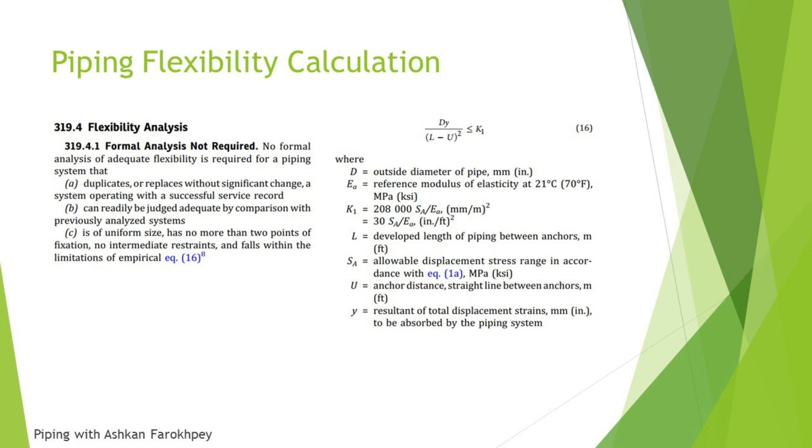In section B, the code says that a new system can readily be judged adequate by comparison with previously analyzed systems. It is just the same as paragraph A, section A. It says that if you have analyzed the system, stress analyzed the system, and you are making a new one just like the first one, you don't need to do stress or flexibility analysis. Both sections A and B are the same I think, because they are saying that if you have a system or you analyze the system and you're making a copy, making a duplicate of that, you don't need to do flexibility analysis. And I think it is something that rarely happens.